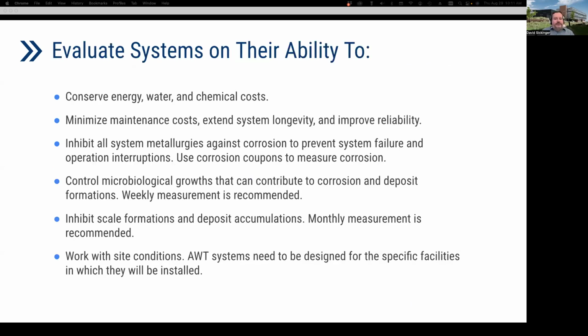So when evaluating systems, I want to consider energy, water, and chemical cost. Proposed system performance should result in a minimum of 15% water savings over current operation. And so part of going through this process is establishing a baseline that you can provide to the AWT vendors. Want to minimize maintenance costs, ask whether options exist, such as self-cleaning.